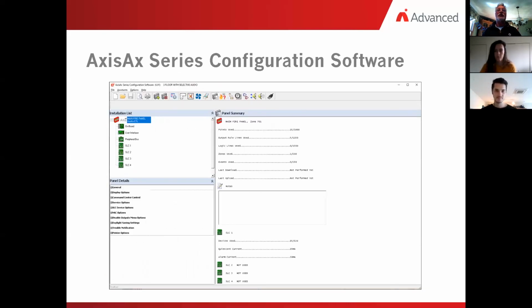Let me show you. This is a screenshot of the AX series configuration software. A couple of things that we have in here: we're going to select the P-bus and add some devices there. We're also going to click on the patterns. The patterns are how we determine when something happens. In the pattern, we select the specific message in an amplifier to play. And then we also have what's known as the output groups. In the output groups, this is how we determine how the system is going to work, whether it's going to be a general alarm activation or a selective signaling. What I mean by selective signaling is when the fire alarm goes off on a floor, it'll activate on the floor of the incident, the one below it, and the one above it.